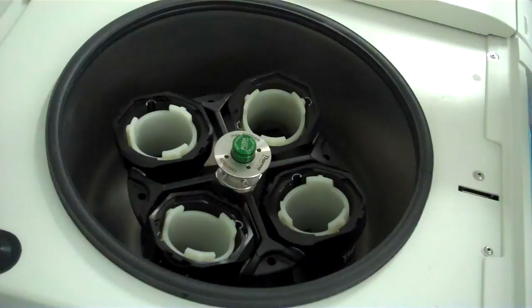All right, let's take a look inside a centrifuge. This centrifuge has a swinging bucket rotor in it, and this particular rotor accepts bottles that contain 250 milliliters of liquid. So this rotor would accept these bottles, which when placed inside would then, once it begins to spin, apply a centrifugal force to the samples, and the buckets themselves begin to fly out, similar to a carnival ride.